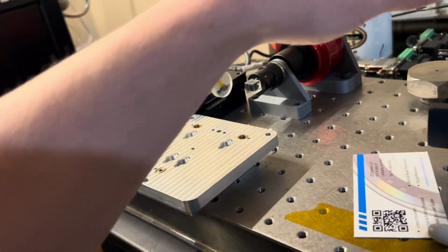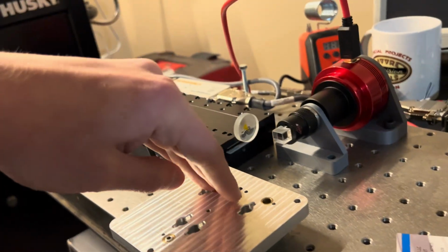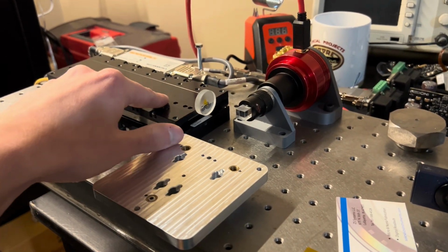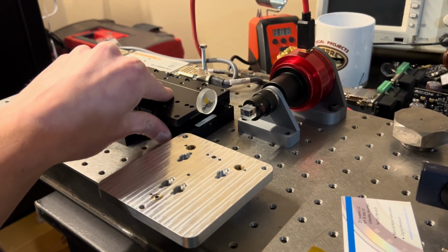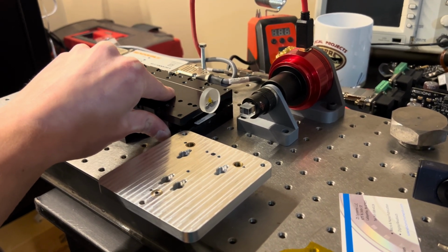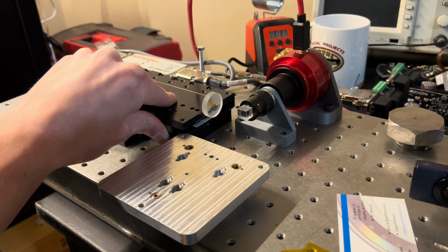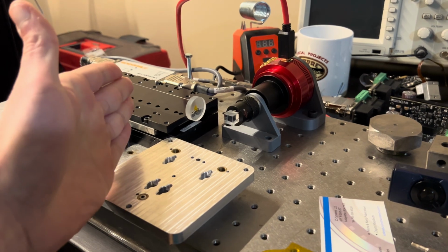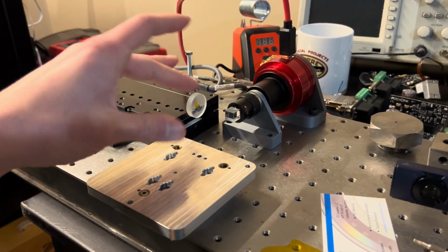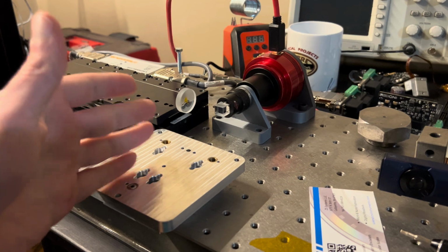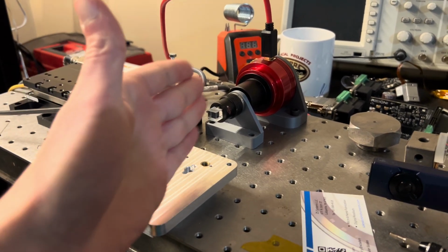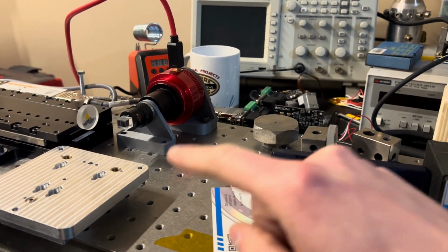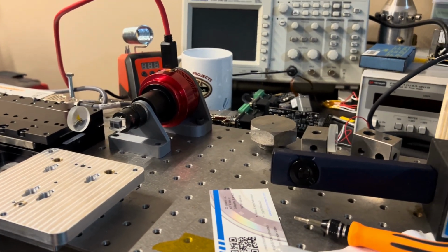The way I'm doing that is the method where you have your sample here, and we're moving the reference arm here, and we focus on the sample and then sweep the reference arm at a very slow, very constant, consistent speed, basically starting on one side of 0 path length difference between the two arms and then going to the other side. So all the way from no fringes to no fringes again. So we get this sort of little chirp of interference because the coherence length is low.